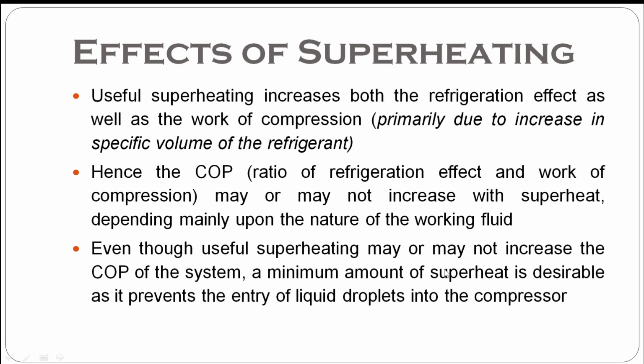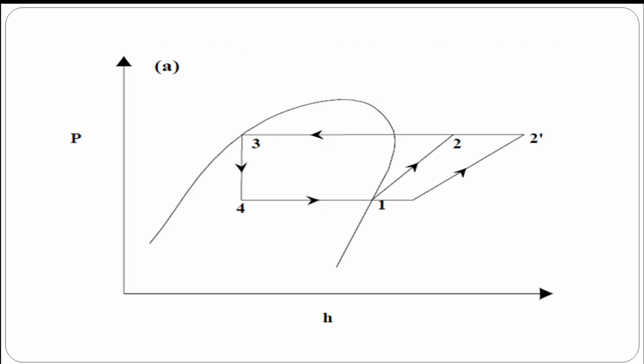Even though useful superheating may or may not increase the COP of the system, a minimum amount of superheat is desirable as it prevents the entry of liquid droplets into the compressor. So in order to ensure only vapor refrigerant enters the compressor, a minimum degree of superheat is required. So you can see here, the refrigeration effect as well as the work of compression, both are increased.